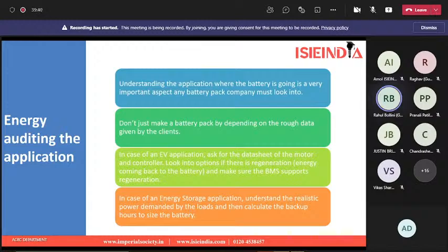In an energy storage application, you need to understand the client's realistic backup hours. Suppose they say they want 2 hours of backup, but there are energy losses due to the inverter, so you'll have to study the inverter's efficiency losses. Say it's 95% efficient, so that 5% should be added back by oversizing the battery. This is a common tip I give any beginner making a battery pack.